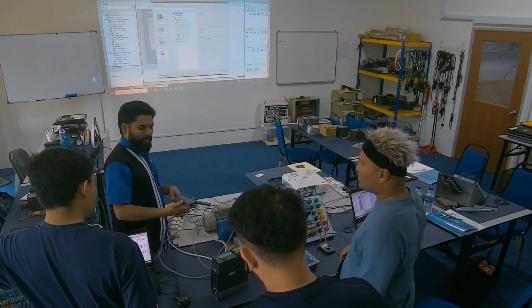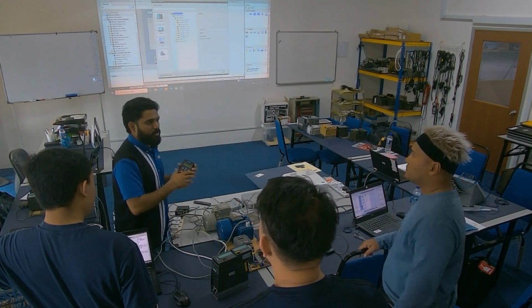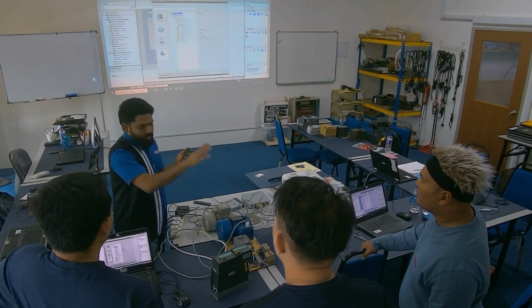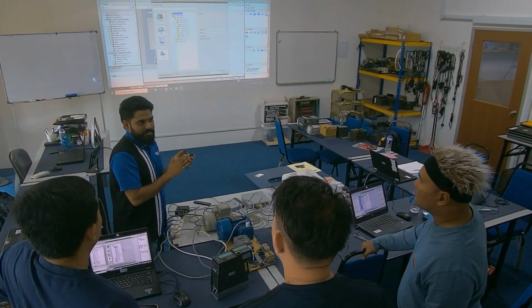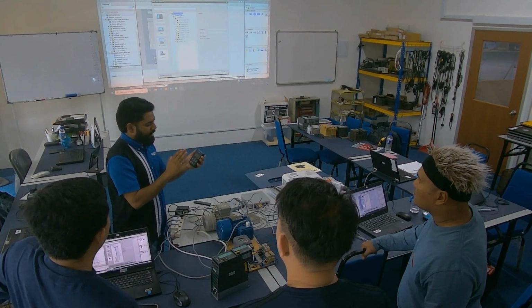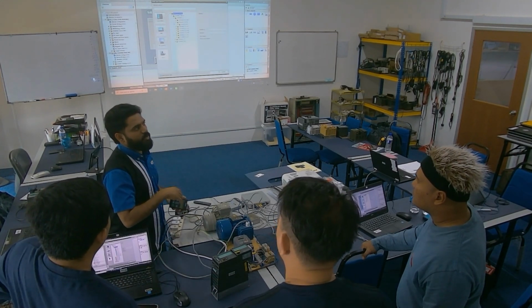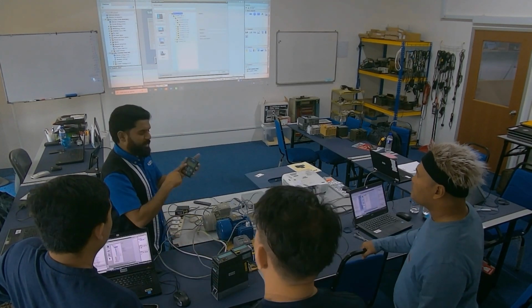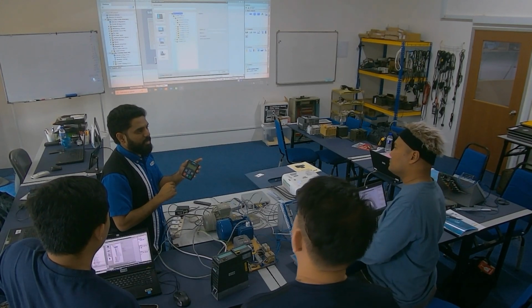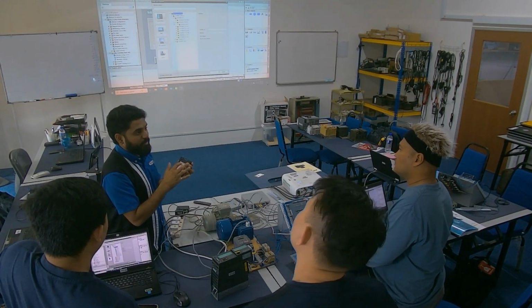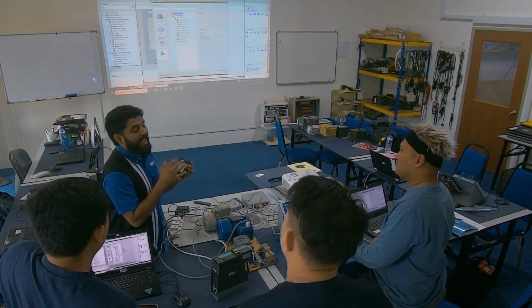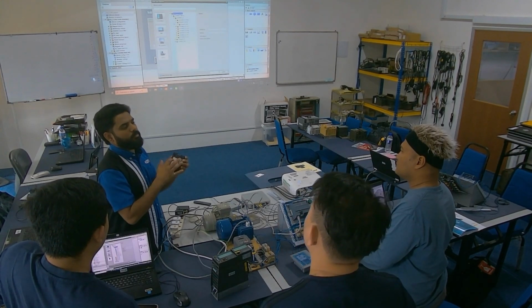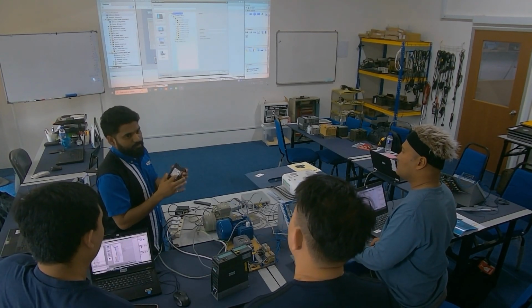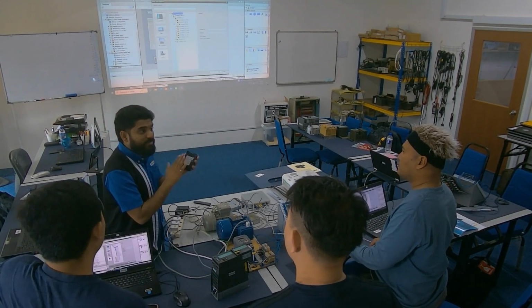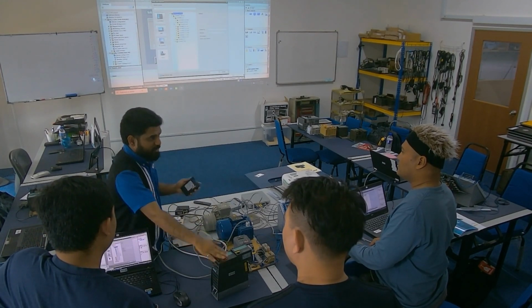So this is normally what they do. If you see sometimes your machine, you have all the VFDs, they have a panel VFD. So actually for let's say you have 10 drives, you only need one. This one is a basic operating panel. There's another one called AOP, Advanced Operating Panel, which has more functions, more settings you can do. This one can even copy the program from here and store it here.